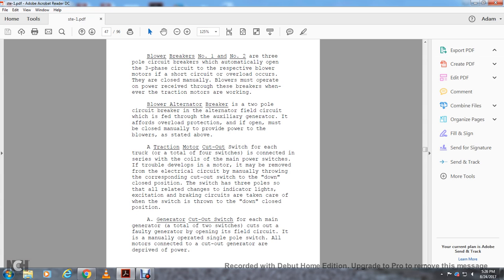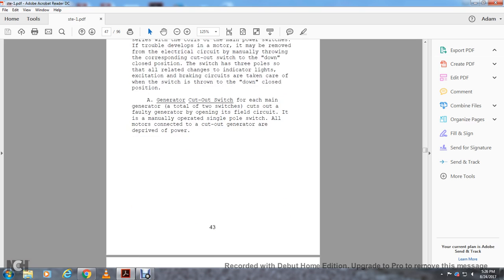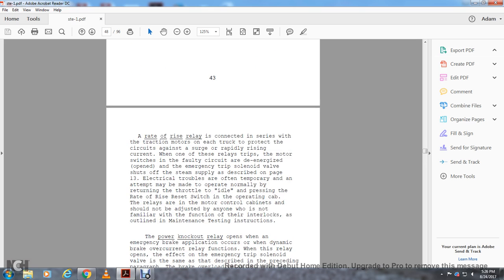A generator cutout switch is provided for each of the main generators, a total of two switches. It cuts out a faulty generator by opening the field circuit, manually operated with a single pole switch, and all motors connected with the cutout generator are deprived of power. A rate of rise relay.